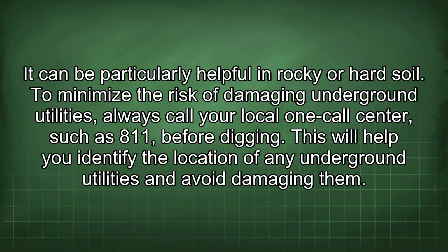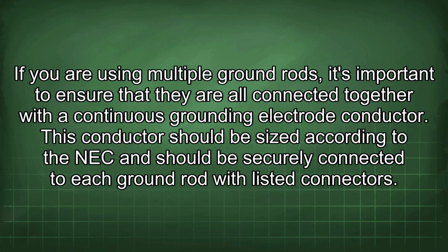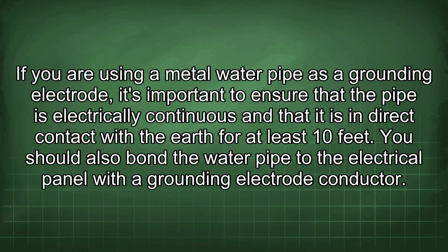To minimize the risk of damaging underground utilities, always call your local one-call center, such as 811, before digging. This will help you identify the location of any underground utilities and avoid damaging them. If you are using multiple ground rods, it's important to ensure that they are all connected together with a continuous grounding electrode conductor. This conductor should be sized according to the NEC and should be securely connected to each ground rod with listed connectors.